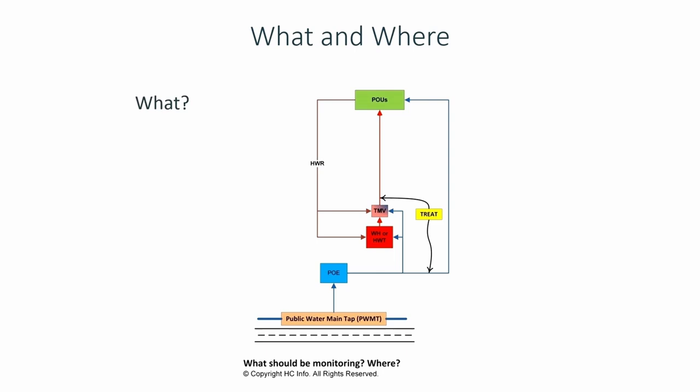You can probably guess some of these, because if you've read much at all about Legionella, you know it's affected by temperature, by the levels of disinfectants, and the disinfection effectiveness — for some disinfectants, especially chlorine, and to some extent chlorine dioxide, monochloramine, and copper-silver ions — are affected by pH. So pH is commonly recommended as well. What other parameters can you think of that might give you an indication of how to manage your water systems for Legionella control? Maybe sediment — like particulate?